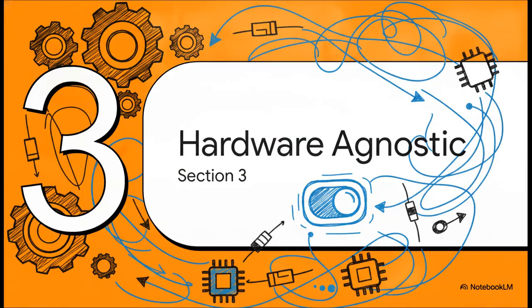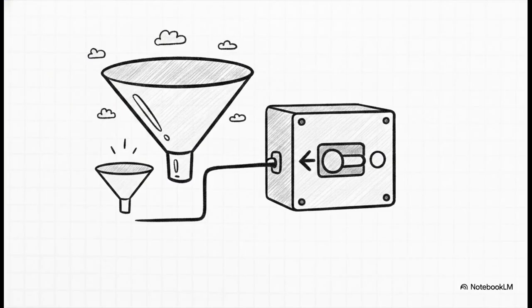Okay, moving to Part 3, hardware-agnostic, software-defined. A lot of engineers assume that if you have different CT outputs in your yard, like say some are rated for 1 amp and others for 5 amps, you automatically have to order completely different relay hardware for each setup. But thankfully, ABB gave us the 1/5 amp selectable software setting. This one simple software toggle makes the relay hardware totally agnostic to the specific CT secondary rating.